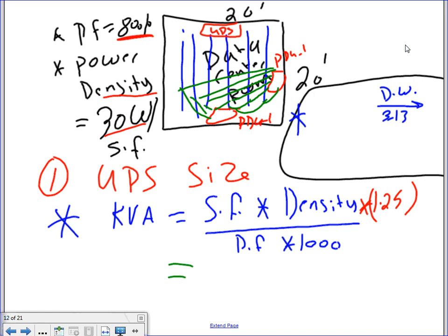Now, here's the formula that I would like to use, guys. Here's what's given. These, you have to get from the engineers. I'm going to change this power factor, guys, to 0.9. Can you change that one? I know yours says, change this one to 90%. My servers have a 90% power factor. There's something called power density, Karen. It's 30 watts per square foot, which is very small compared to what they do right now, but this is the example. Based on these criteria, can you also change this one, guys? Erase this one here. And right now here, add losses, multiplied by the losses factor. Okay, so I would like you guys to do that. Change them, update this information.